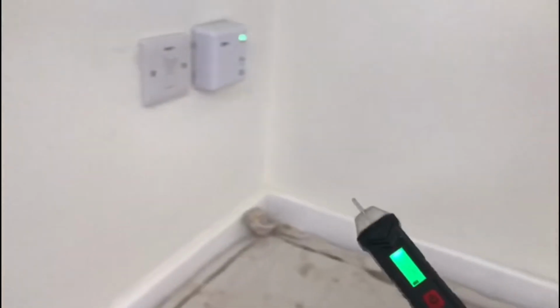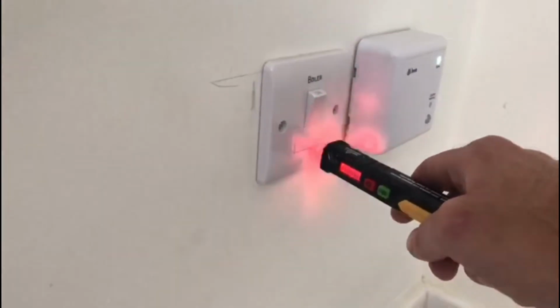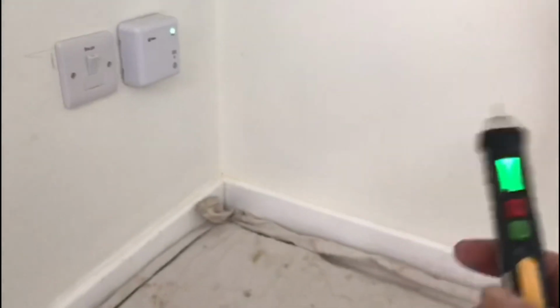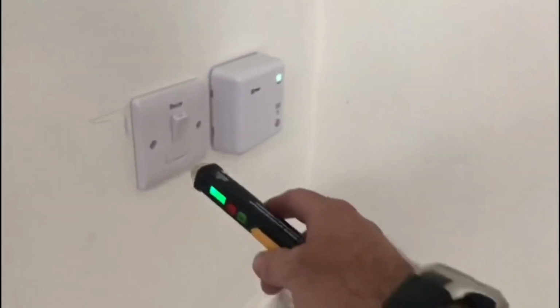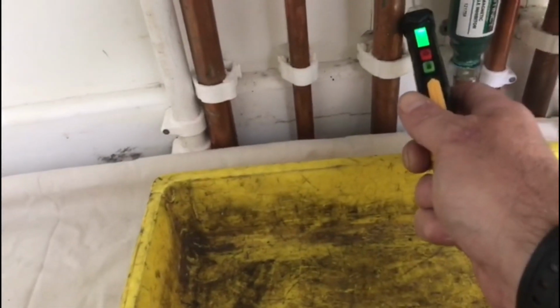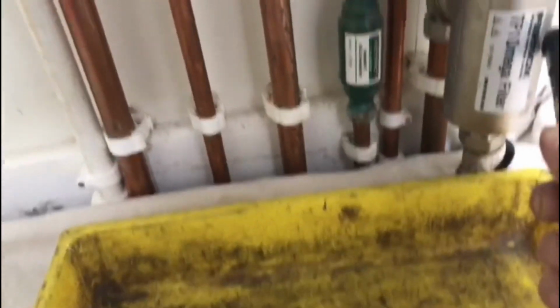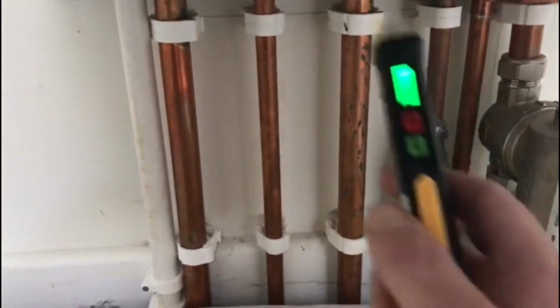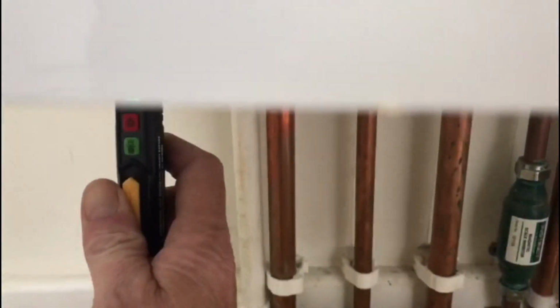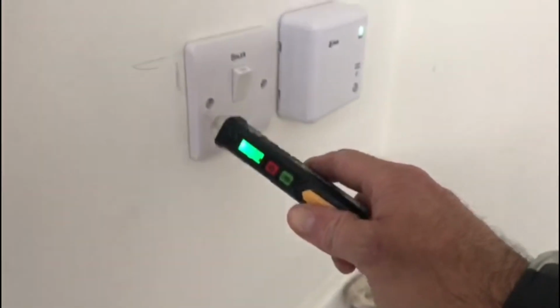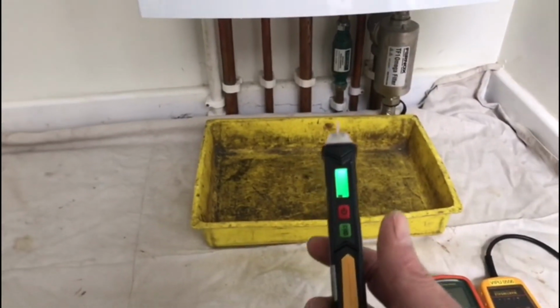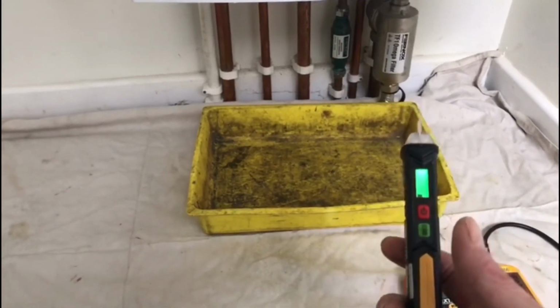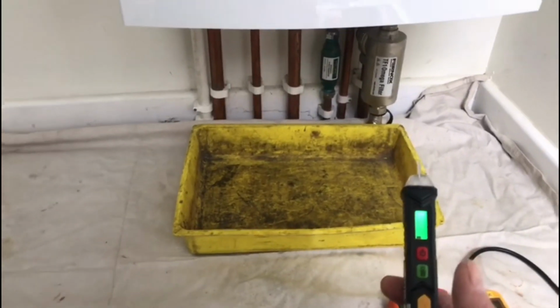And to test a positive source, I'll test the fuse spur of the boiler, which I know is working and it's on. As you see, it indicates there's a voltage, so we know that this unit's working. Test everything again. So any metal part that you're testing around the boiler, test the chassis as well, touch the chassis. It's not showing me a reading. I'll test it again. It tells me that my test is okay. I'm okay to carry on touching the boiler because my non-contact test is passed. So I can touch the boiler with no fear of getting an electric shock.